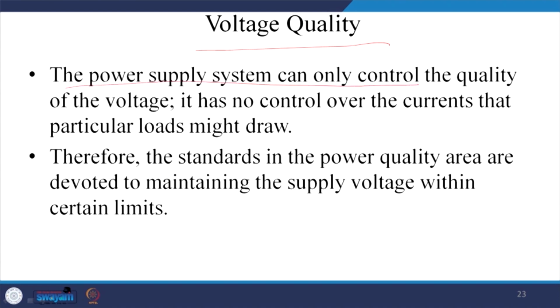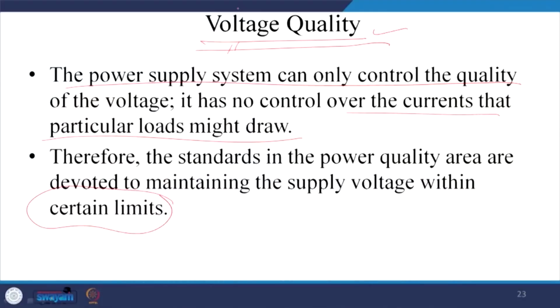The power supply system can only control the quality of the voltage, it has no control over the current. Generally the load will decide the amount of current that the particular load might draw. Therefore, the standards in the power quality area are devoted to maintaining the supply voltage within certain limits. So, we require to maintain the voltage quality, and in most cases we have a voltage source. A current source we have to make artificially, otherwise we do not have a current source, and for this reason the source is voltage. If there is a problem of the voltage, then of course there will be a problem of the power quality.